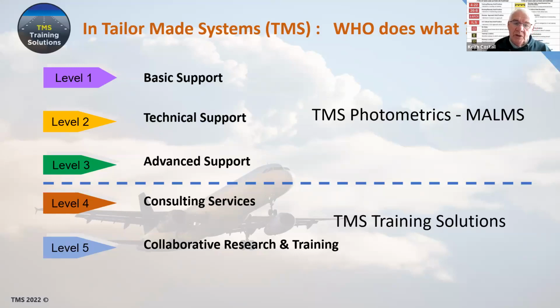For example, we have moved from tungsten halogen to LED. We have moved to advanced surface movement guidance technologies. We've moved from single control lines to power line communication. That in itself has brought a lot of demands, because why? We have a problem collectively in an AGL system, because over the world we have generally adopted a 6.6 amp constant current electrical system. Now, that's not exclusive. There are other systems out there in today's technology, but standardized around the world is a 6.6 amp constant current system.